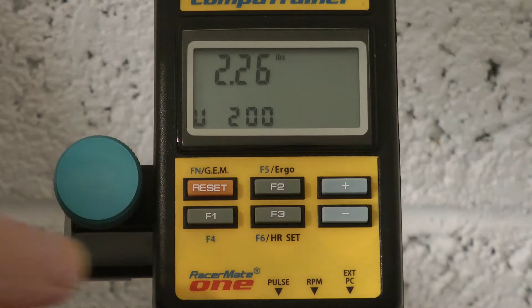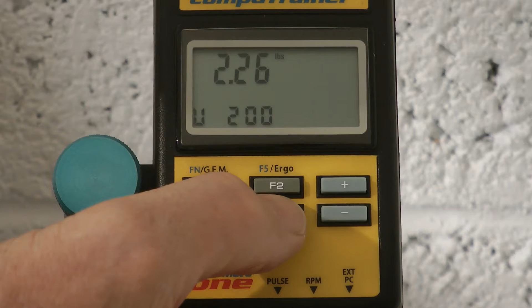There we are, I've stopped. It's now calibrating it, measuring the press-on force, rolling resistance. You can see at the moment it's saying there is 2.26 pounds of press-on force. So what I have to do now is press F3 to save that number. You'll see the bottom value change. There we are.